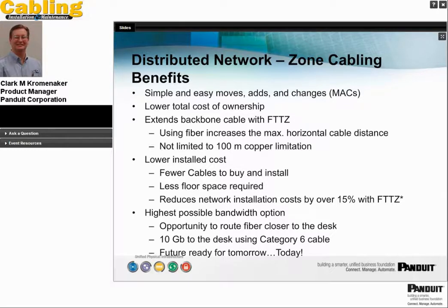Lower installed cost: there are fewer cables to buy and install. If you run one of these trunk cables to an active zone enclosure, you're going to have less copper, because you're either going to have a couple cables of copper or even one pair of fiber going to that zone enclosure with the active equipment.